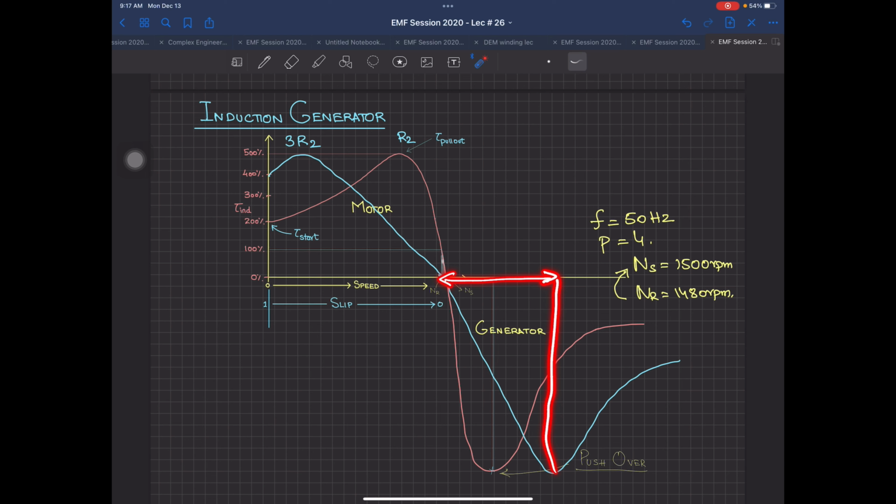And this will be beneficial. Why? Because the wind is not flowing at a constant speed. It's variable. So you don't need a big gearbox. Because if you have to attach a gearbox, your speed should remain inside this range. And you always know mechanical gearboxes always have some efficiency loss. It's not going to be always 100%. There is going to be some loss.